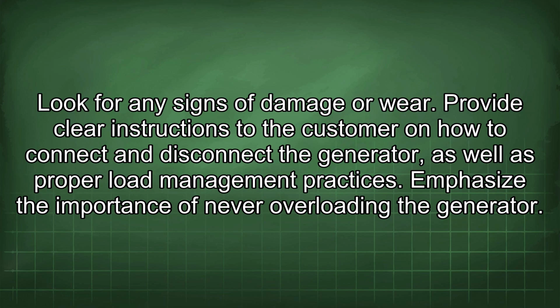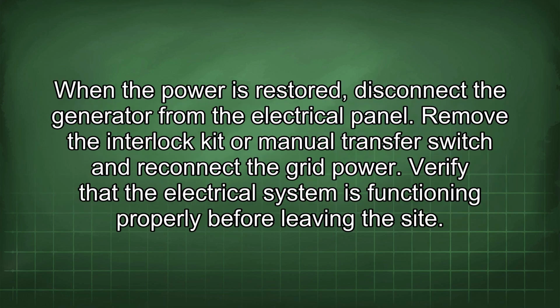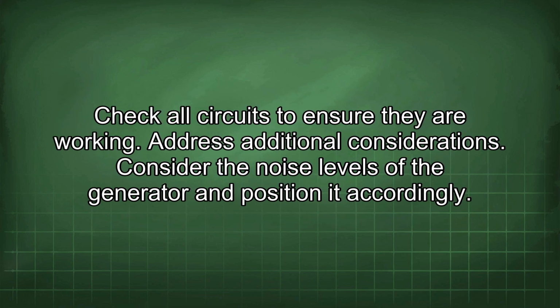Emphasize the importance of never overloading the generator. When the power is restored, disconnect the generator from the electrical panel. Remove the interlock kit or manual transfer switch and reconnect the grid power. Verify that the electrical system is functioning properly before leaving the site. Check all circuits to ensure they are working.